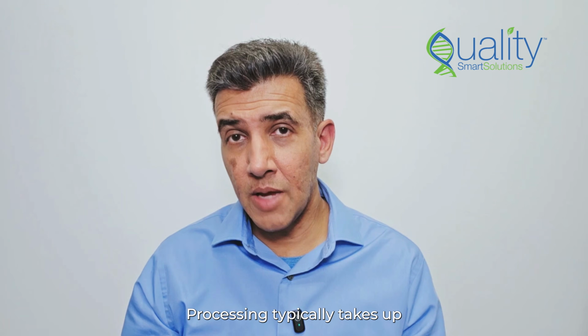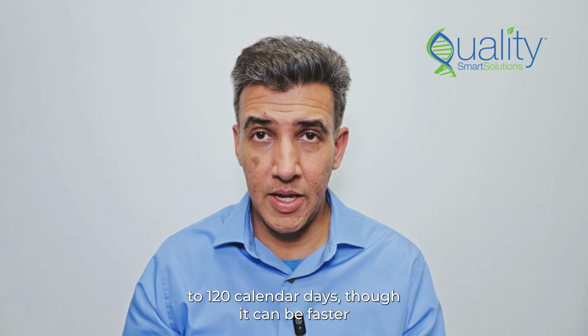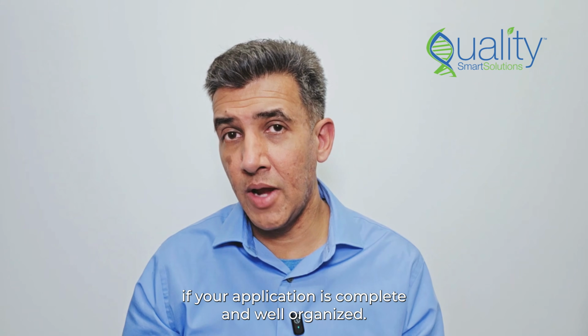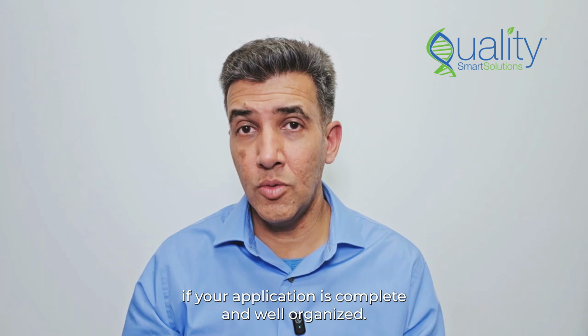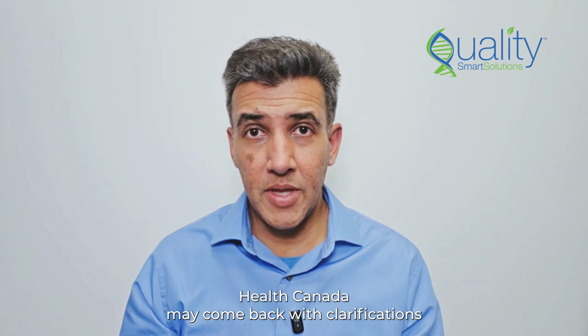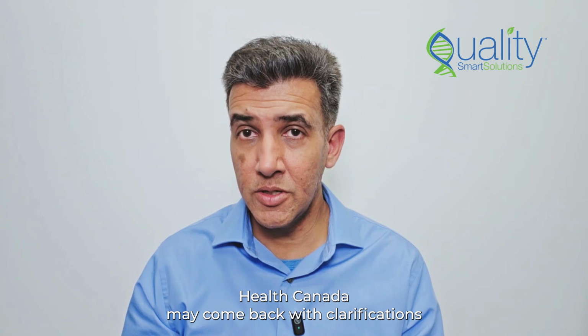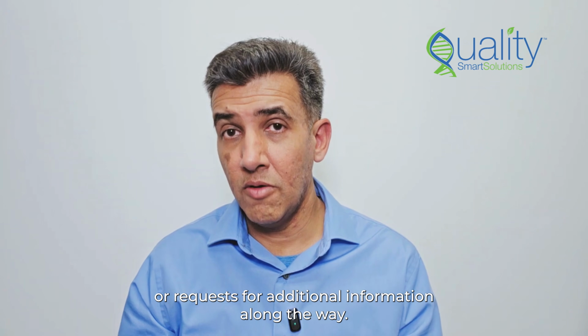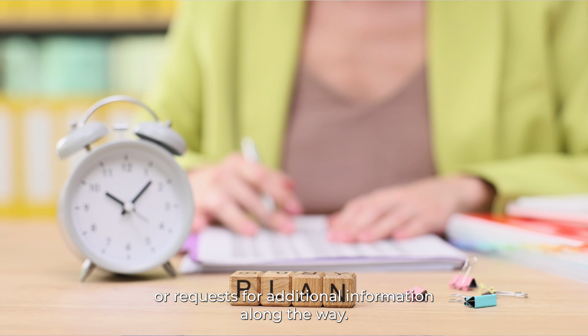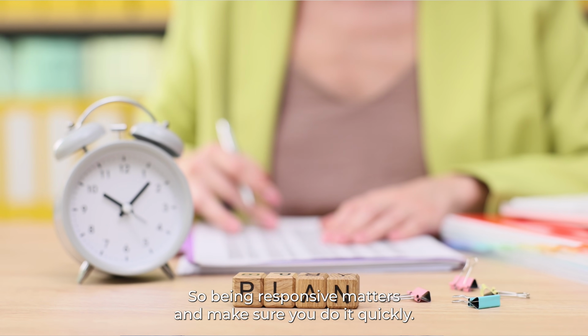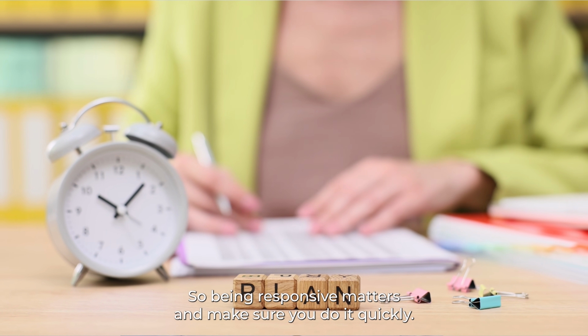Processing typically takes up to 120 calendar days, though it can be faster if your application is complete and well organized. Health Canada may come back with clarifications or requests for additional information along the way. So being responsive matters, and make sure you do it quickly.